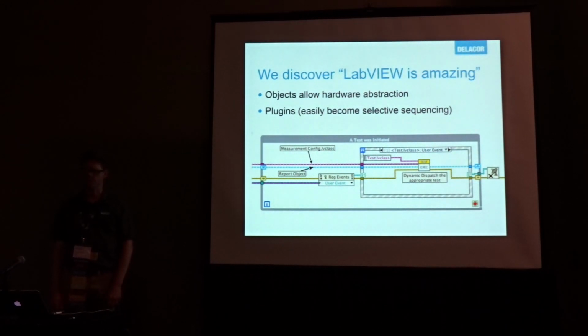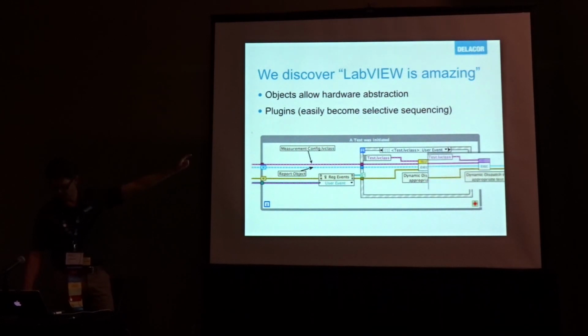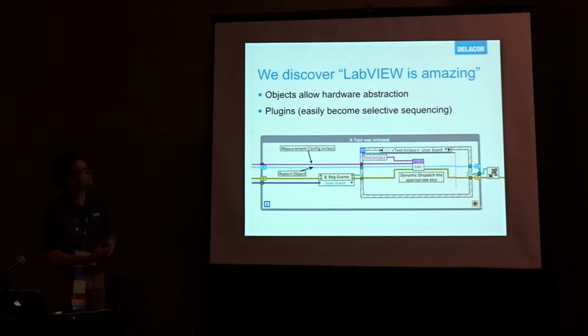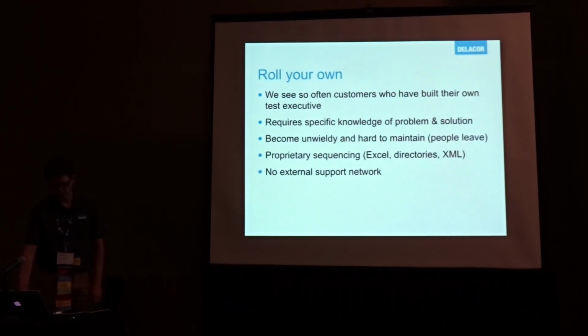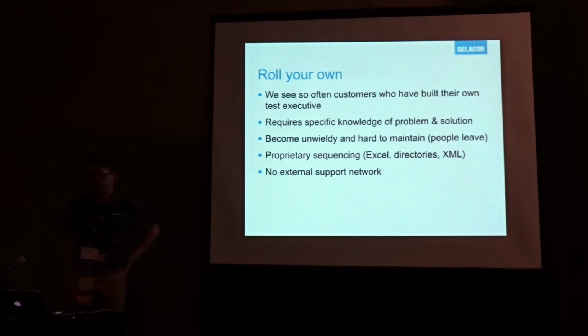Then we discover LabVIEW is amazing. We start using things like object-oriented LabVIEW, where we can abstract the hardware away from our test solution. We can start plugging in different models of instruments, or plugging in different tests. So in this particular code, I've got a loop running, and at runtime, I'm using dynamic dispatch to call different tests. So these plugins allow me to do selective sequencing. At runtime, I can choose to perform different tests.